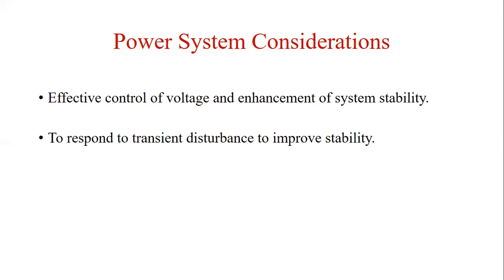Excitation systems have since undergone continuous revolutions. In the early 1960s, the role of the excitation system was expanded by using auxiliary stabilizing signals in addition to the terminal voltage error signal to control the field voltage to damp system oscillations. This part of excitation control is referred to as the power system stabilizers. Modern excitation systems are capable of providing practically instantaneous response with high ceiling voltage. The combination of high field forcing capability and the use of auxiliary stabilizing signals contribute to substantial enhancement of overall system dynamic performance.